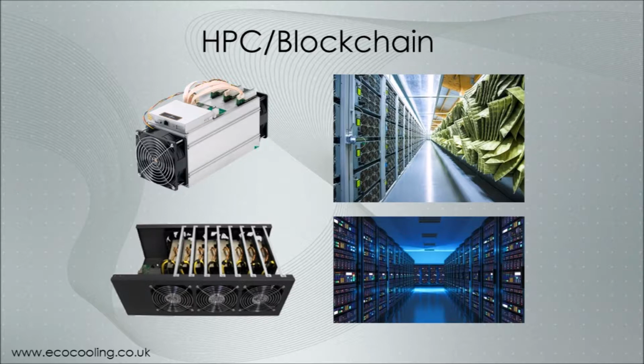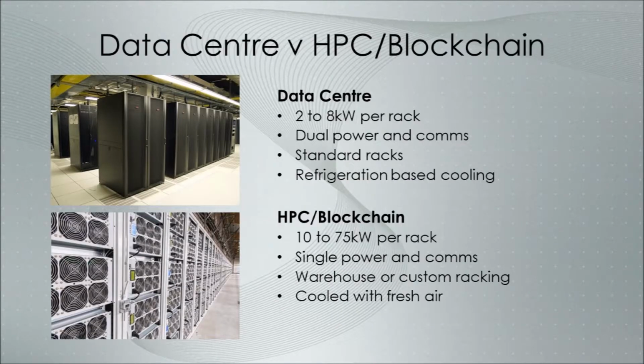So what we're looking at are the cooling issues we've got to address. In a normal data center you'll see typical 32 amp, 16 amp racks, up to 8 kilowatts. The average density in the UK, I'm told, is 2 to 3 kilowatts per rack in standard co-location or enterprise data centers - very few people stack up the full 32 amps to make 8 kilowatts. Lots of resilience in your normal data center: A and B power, A and B comms, N+1 cooling, 2N cooling, 2N+1 systems, tiers 3, 4, that type of uptime. What do we see with high performance computing and blockchain?